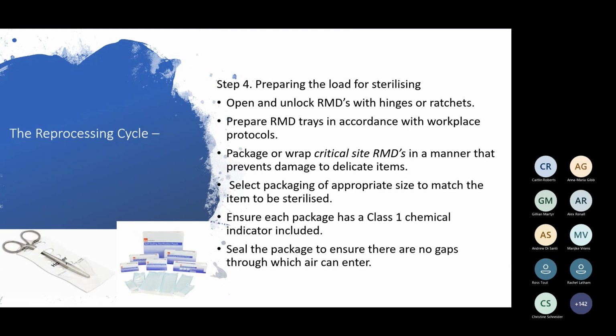It's going to be puffed right to the edge. So if you are overpacking your bags or putting instruments right up to the sides of the bags, you can potentially split the bags. So make sure you pick the right bag for the job. Make sure that each package has a class 1 chemical indicator and seal the package to ensure there are no gaps through which air can enter.